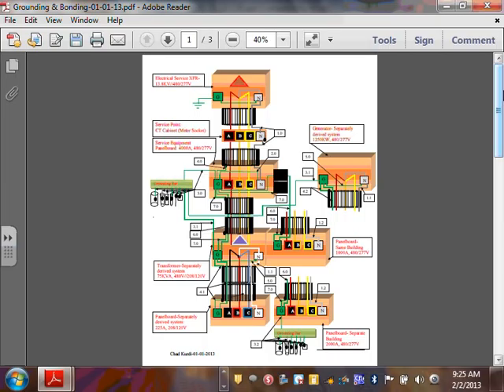So everybody understand what this block is? This is the utility service, the service coming to your buildings. Cool? Now from the service coming to your building, I have 480/277. I'm coming into the CT cabinet. You guys are familiar with the CT cabinet, or termination box. So you're coming into the CT cabinet here, or termination box, where you can meter the power that's coming into your building. And we'll see how we'll bond and ground around this one.